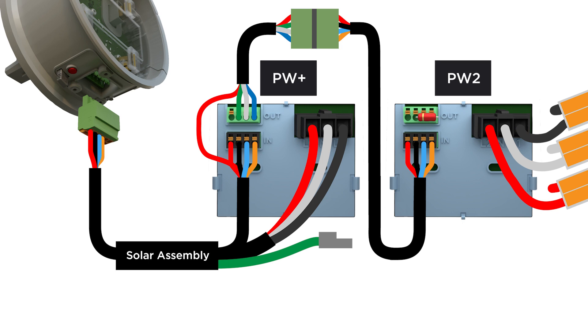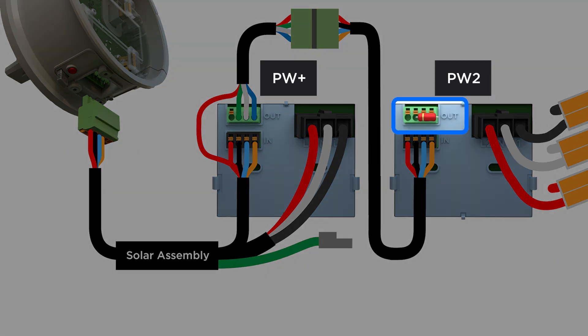Continue this pattern of out to in for each additional Powerwall 2. Install the end-of-line resistor in the out port of the last Powerwall 2.